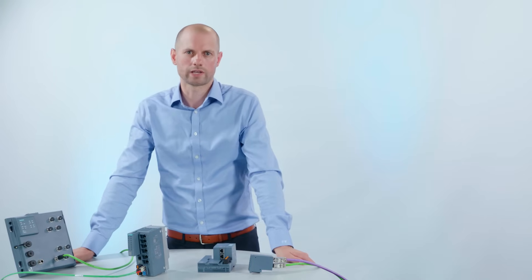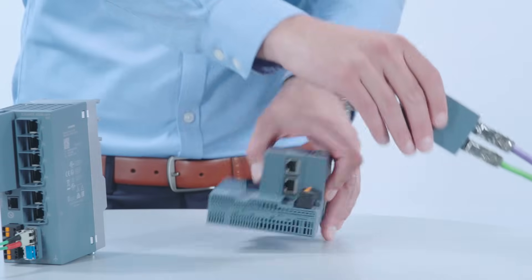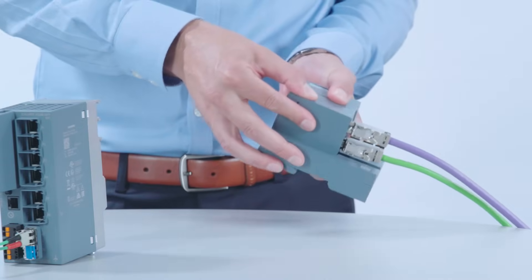VD stands for variable distance and variable is the right word to describe it. With these VD adapters, communication is supported via 2, 4 or 8 wire cables and distances up to 1000 meters can be bridged. This enables you to continue to use your installed PROFIBUS cables for PROFINET.